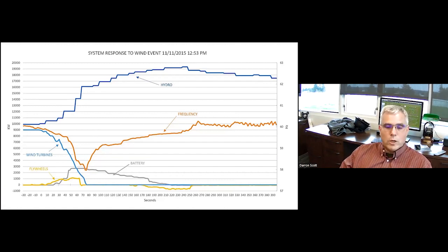The reason we really keep the diesels on board is our hydro plant is about 20 miles away, remote, and the power line goes over a mountain pass into town. Just like another location had several years ago, we can get heavy icing on our transmission line in the mountain pass. So we run a full fleet of diesels here in town that would provide backup in case Terra Lake was unavailable for a long period of time. We only run those basically quarterly to make sure they work.